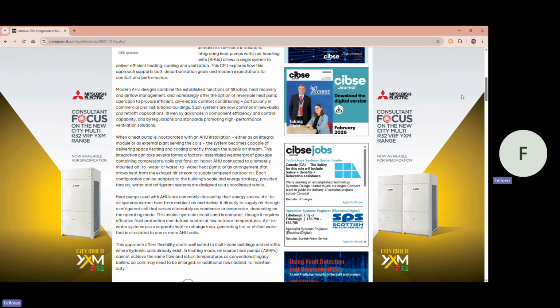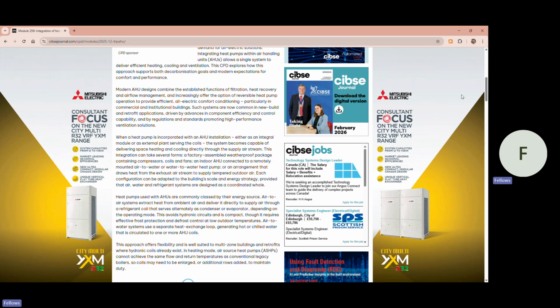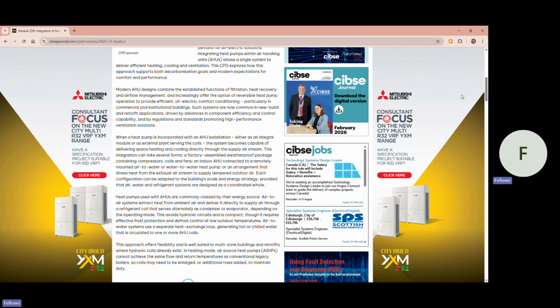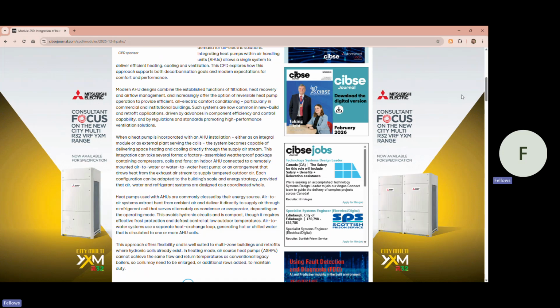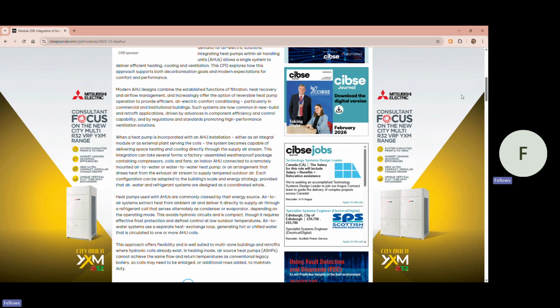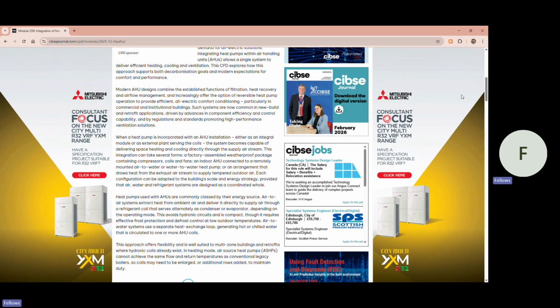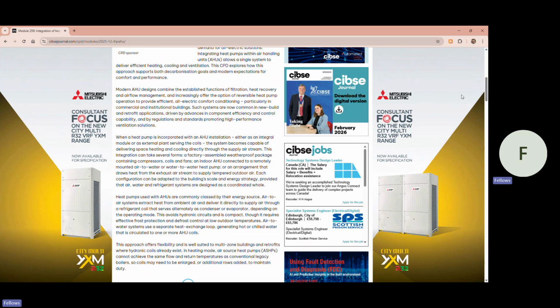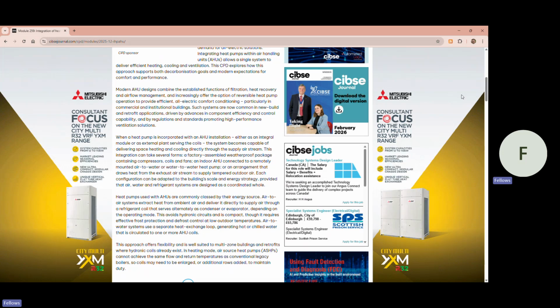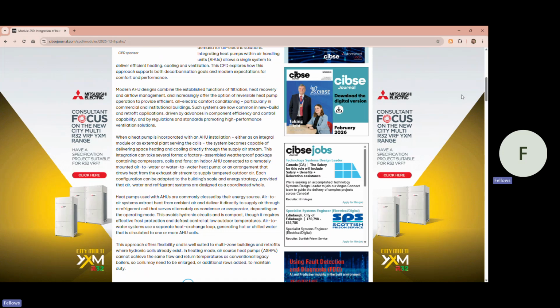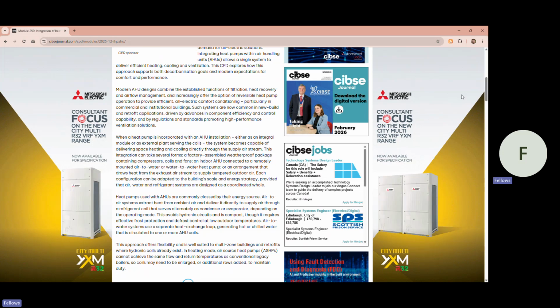When a heat pump is incorporated within an AHU installation, either as an integral module or as an external plant serving the coils, the system becomes capable of delivering space heating and cooling directly through the supply airstream. This integration can take several forms: a factory-assembled weatherproof package containing compressors, coils and fans, an indoor AHU connected to a remotely mounted air-to-water or water-to-water heat pump, or an arrangement that draws heat from the exhaust airstream to supply tempered outdoor air. Each configuration can be adapted to the building's scale and energy strategy, provided that air, water and refrigerant systems are designed as a coordinated whole.